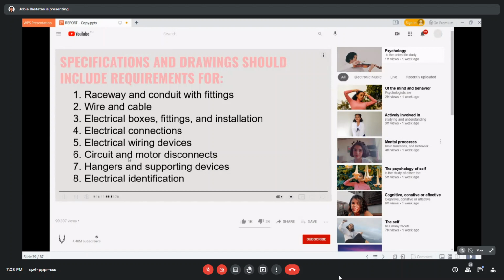Third, electrical boxes, fittings, and installation. Electrical codes generally require that all electrical devices and the wiring connections to those devices must be enclosed in an approved electrical box. Fourth, electrical connections. Electrical connections are any structures that allow electricity to flow in it. Five, electrical wiring devices. These are the finishing touch and a chance to test all branch circuits for proper operation. Six, circuit and motor disconnects. All disconnect switches will be strategically placed where they can be easily accessed by maintenance personnel without the use of a ladder or traversing other equipment.